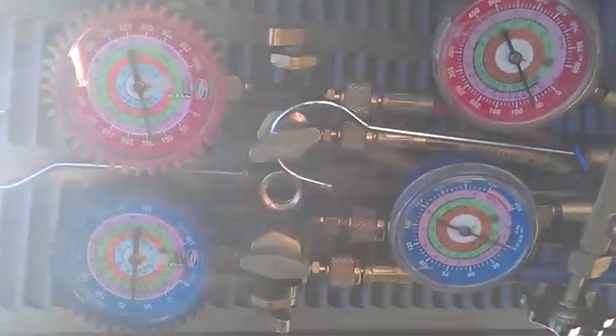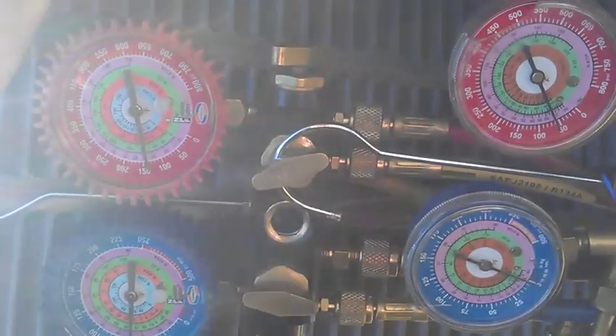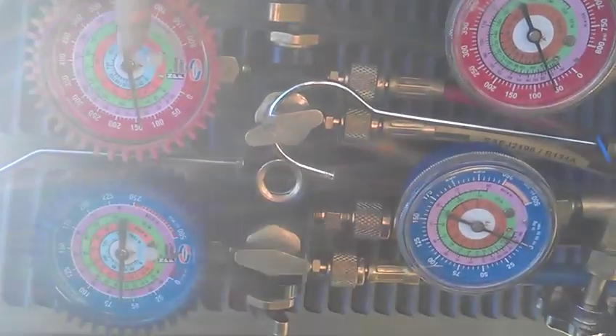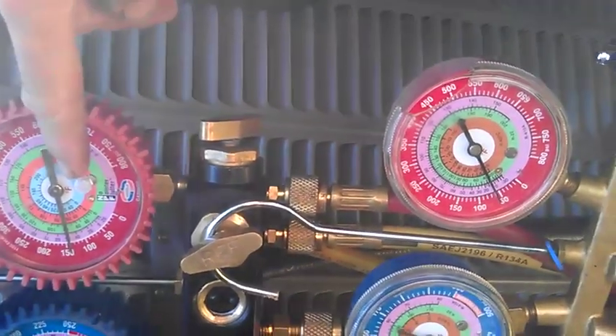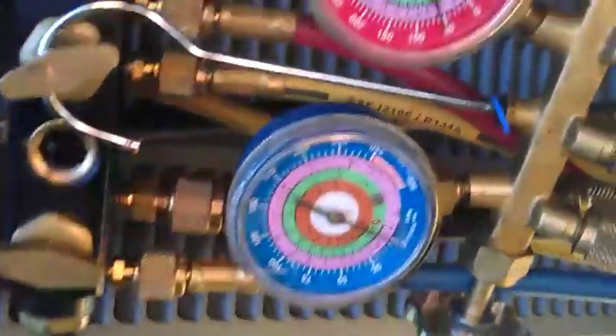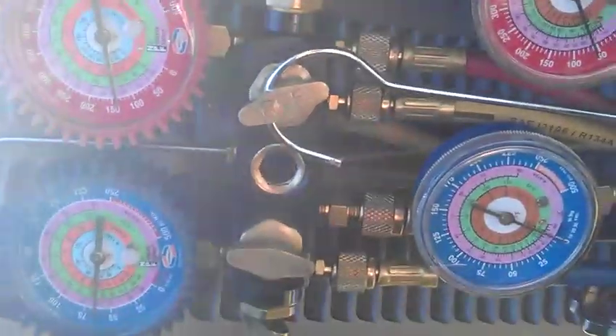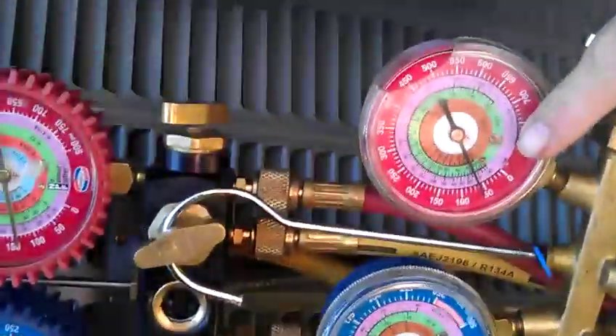Now this gauge here is not being used for anything, so totally ignore it. This gauge is true suction. This one is my liquid line and this one is hooked to the suction line over here on the system like I showed before.